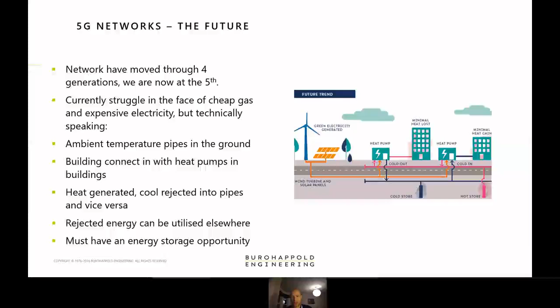Importantly, with an ultra low temperature network you can genuinely recover secondary heat. You don't need a certain grade of heat, because your carrier fluid is low enough to accept all sorts of heat and cooling as you balance the network. That's a problem with a fourth generation system: if your supply temperature is 60 degrees, to recover cooling you need to raise any rejected cooling up to 60 degrees, which is an increased energy cost.